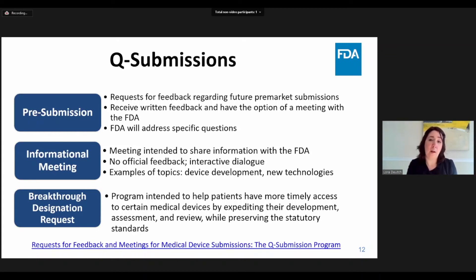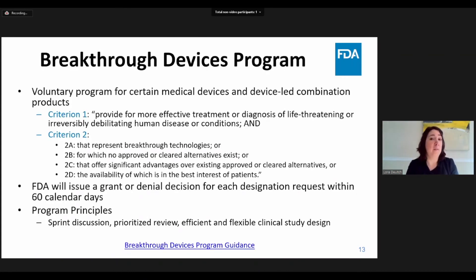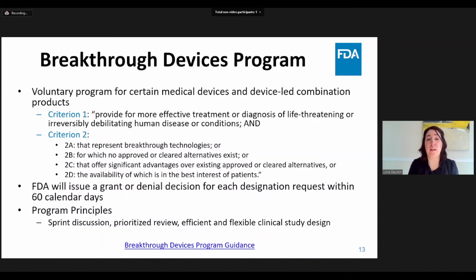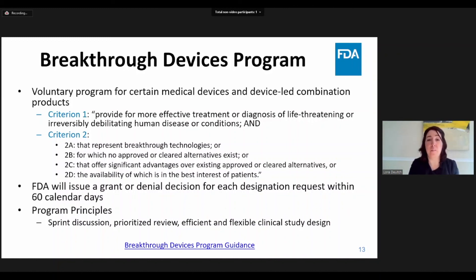The Breakthrough Program is intended to help patients have more timely access to certain medical devices by expediting their review. The Breakthrough Devices Program is a voluntary program for certain medical devices and device-led combination products. A Breakthrough Designation request is a mechanism by which sponsors request entry into the program and FDA renders a decision on the request. To be eligible, the device must meet the first criterion and at least one of the subparagraphs listed in the second criterion shown here. If found to meet breakthrough criteria, FDA intends to help expedite development and review through options such as sprint discussions, prioritizing the review, efficient and flexible clinical study design, and others. A link to the Breakthrough Guidance is included below.